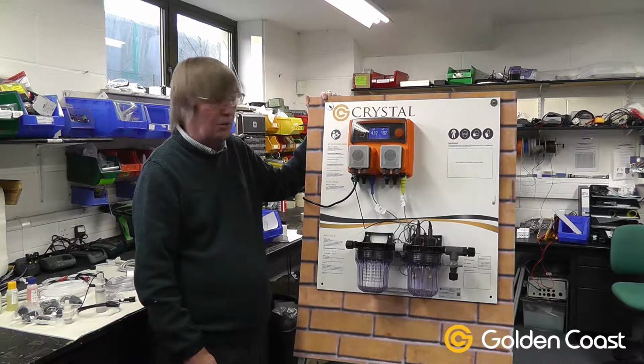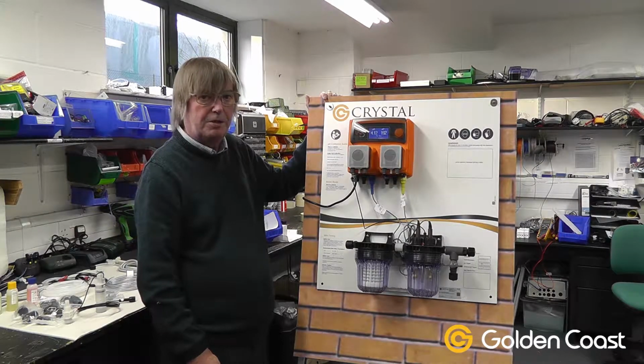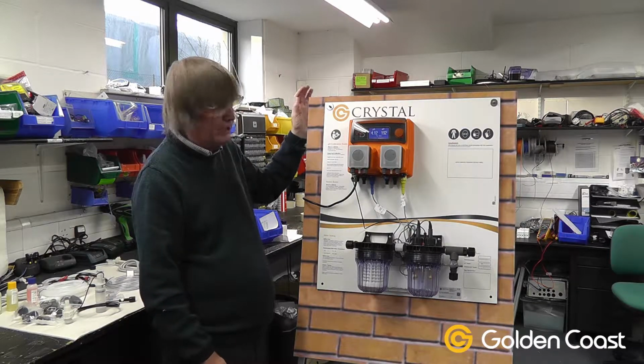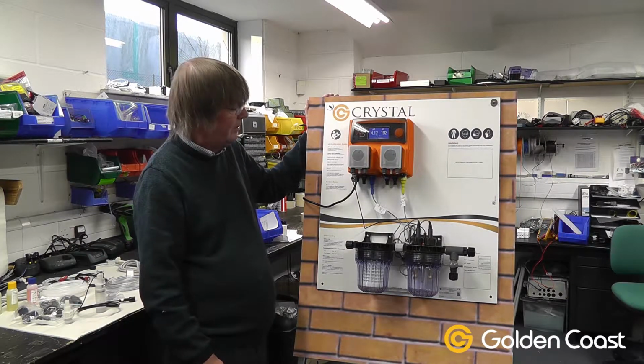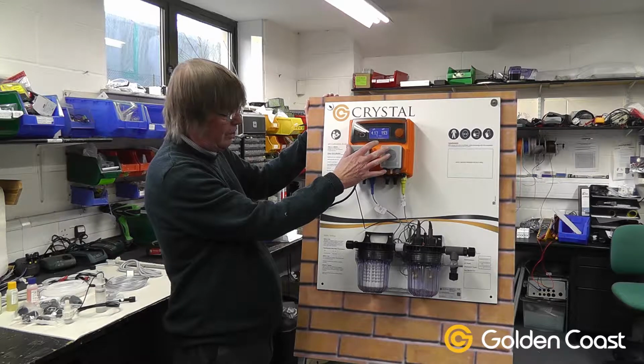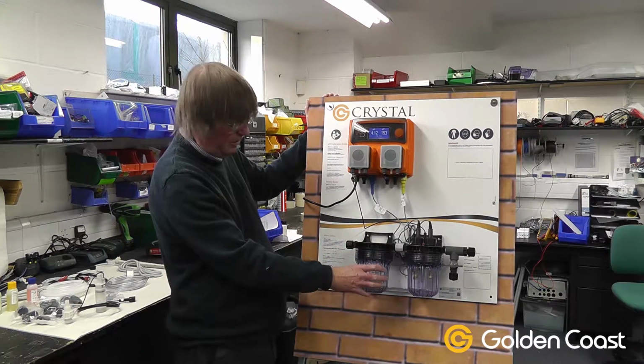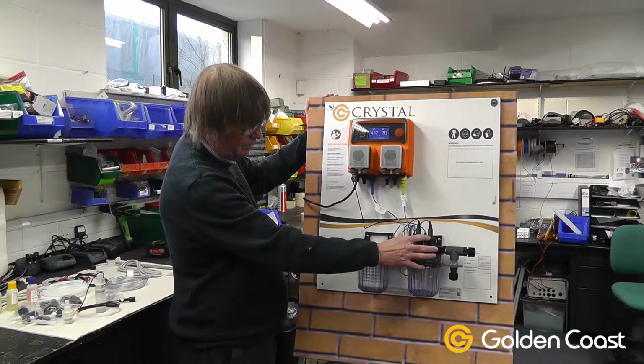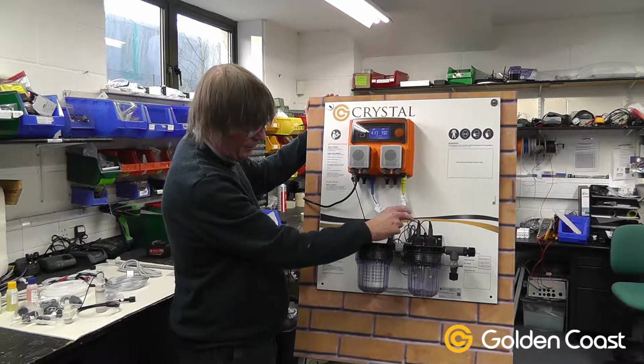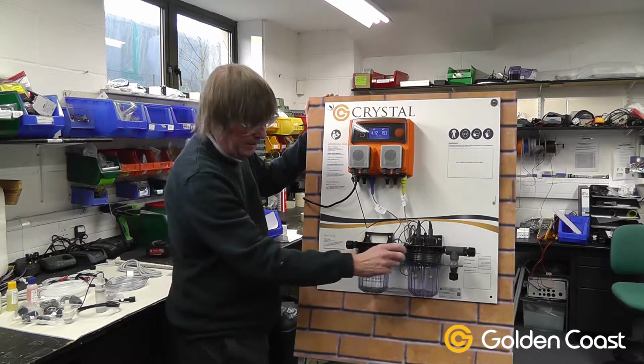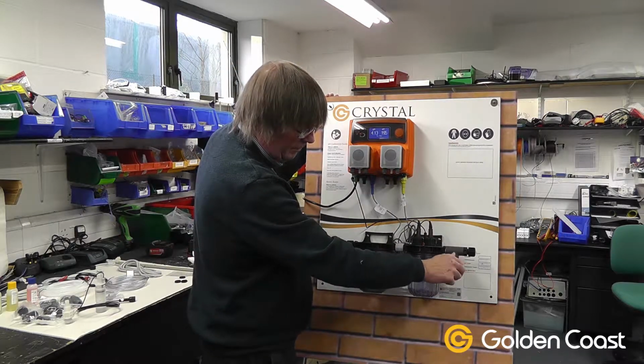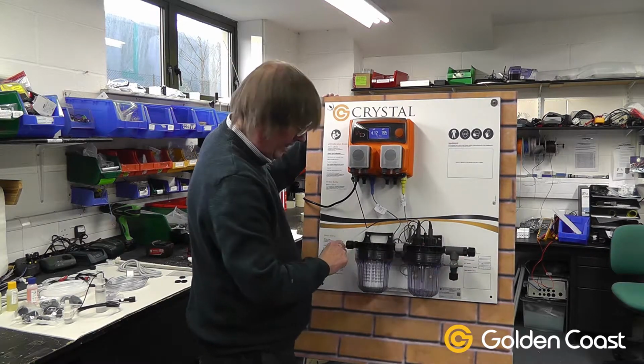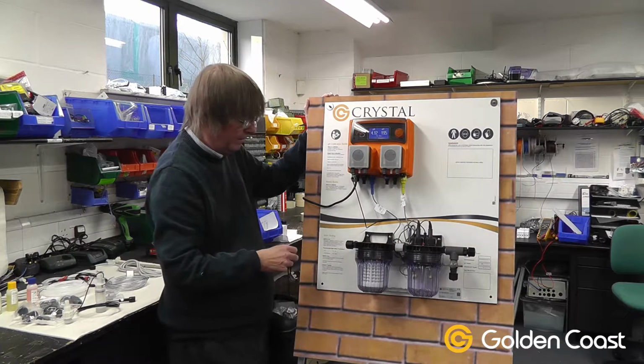Today we're going to be looking at one of the crystal chemical dosing systems for swimming pools. This particular one is the MV type, and it has the chemical controller at the top. Underneath we have the pre-filter to protect the probes. Then we have the flow cell with the two probes, a flow switch, an earthing point, and next to it a place to take a sample if you need to test it. And we have the inlet and outlet for the sample flow line.